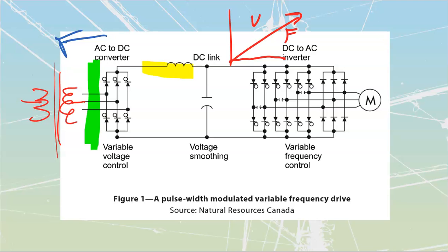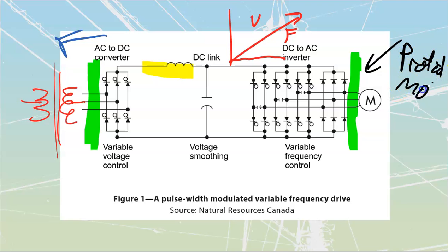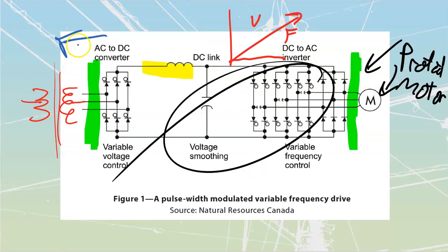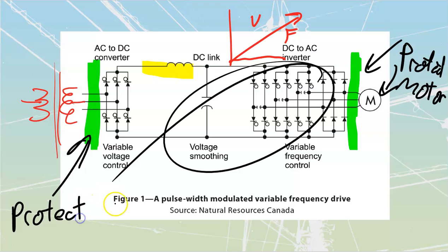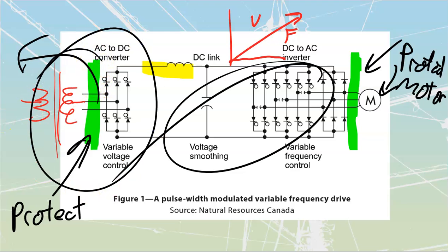Once again, the point of the filtering, this filter over here, is to protect the motor. It's just to protect the motor from anything that's going to be happening inside of the drive itself. The purpose of this filter over here is to protect the rest of the system. Guaranteed, it is more critical to protect the rest of the system, your warehouse, your shop, whatever it is, from the garbage coming off of your VFD. So if you're not going to do anything heroic, then at least, as a bare minimum, do a little bit of filtering on the incoming side.